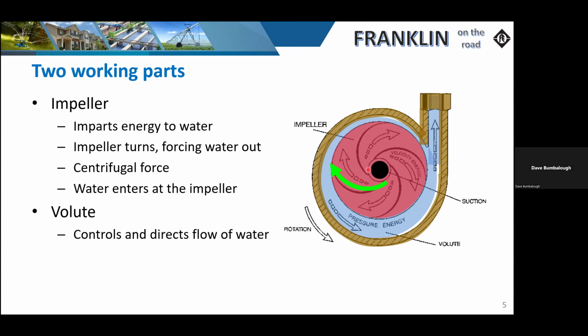So as you notice, the curvatures of these are basically referred to as vanes. If you think about it, there are some pumps out there where the vanes come straight out. Well, if you look at the surface area of that as it comes straight out, it is a lot smaller. And for us to make the pump as efficient as possible, we want to hold on to that water molecule as long as we can. We're trying to make sure that velocity energy is impacting that water molecule as much as possible. So to be able to hold on to that water molecule longer, we put a little bit of a curvature to that vane so we can hold on to it a little longer.